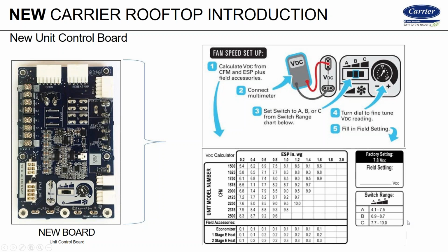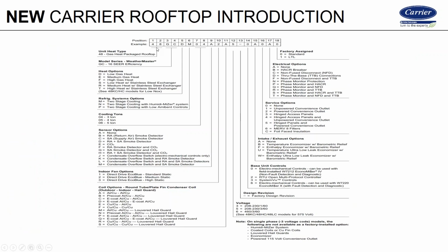That goes back to the model number. Let me see, I may have hidden that slide. Let's take a look. There you go. In this case, I apologize to the Bryant and Day and Night guys, it's a Carrier slide, but both Bryant and Day and Night have a model number alphanumeric breakdown. The 48 series tells us gas heat pack, GC tells us it's 2-speed, and then we start getting into heat exchanger information and all that kind of stuff. You get down to your tonnage, and then right here in position 10 on the Carrier, if you've got a 1, it's going to tell you you've got a standard static. A 2 is medium and a 3 is high.